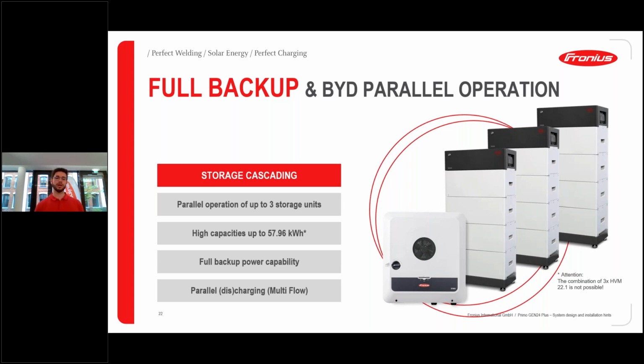And in a backup scenario, we of course need this disconnector switch at the feed-in point that I've mentioned earlier. This is necessary to disconnect the whole system from the grid, and then it restarts its own backup grid and supplies the whole household again with the full nameplate power of the inverter. And then we have, of course, the possibility of multi-flow. So if the sun is shining, we're using PV energy. We're using energy out of the battery, and if we don't need as much energy from our battery, we can also recharge the batteries in backup mode. So a lot of ways are possible here in a full backup scenario.